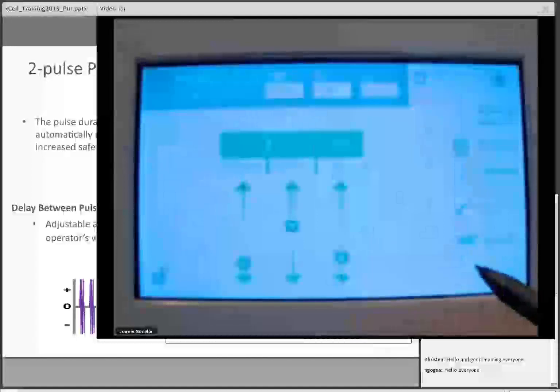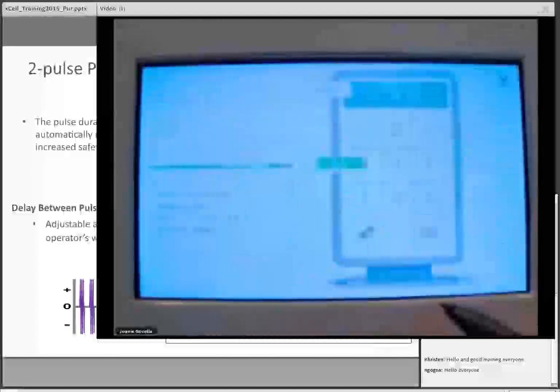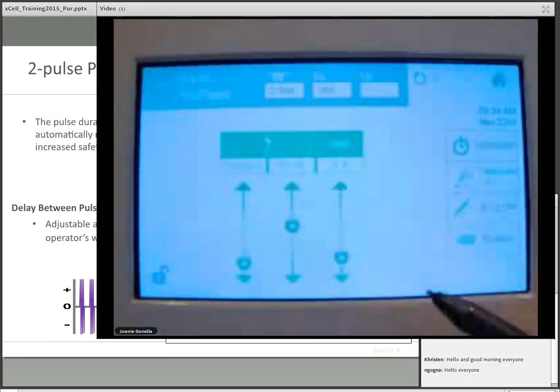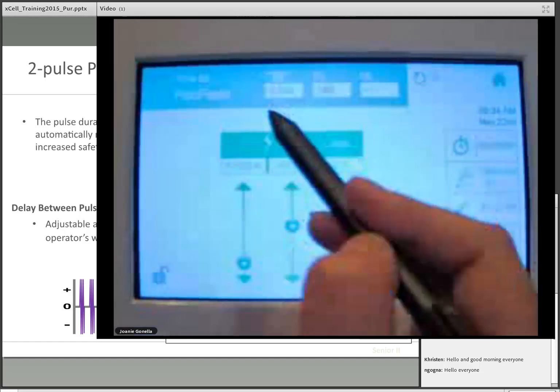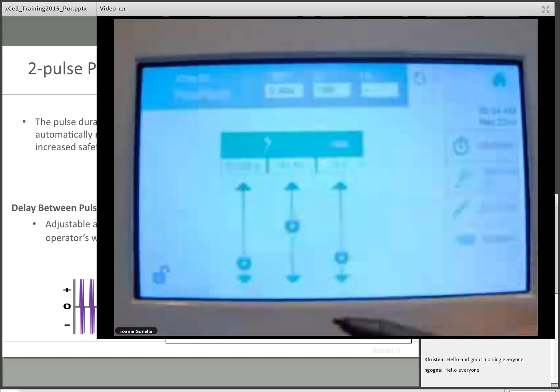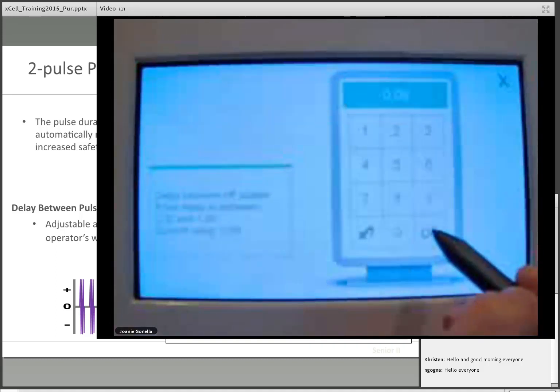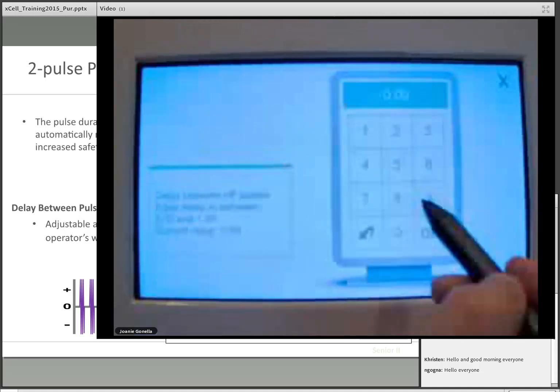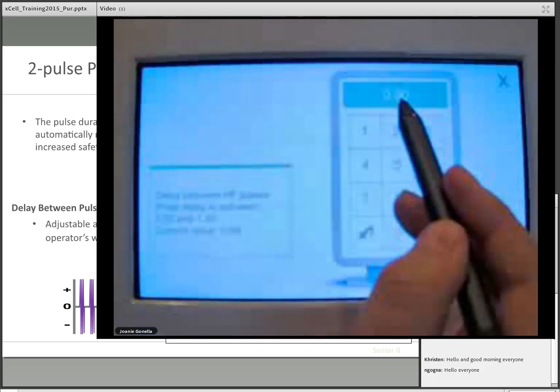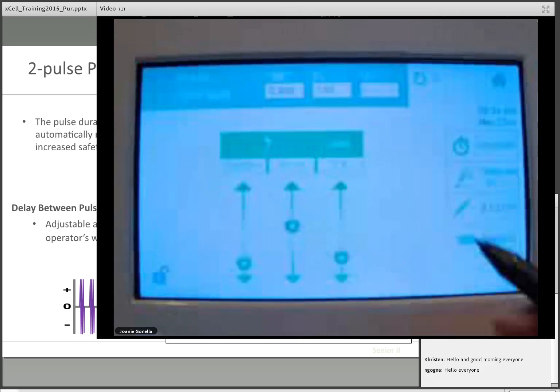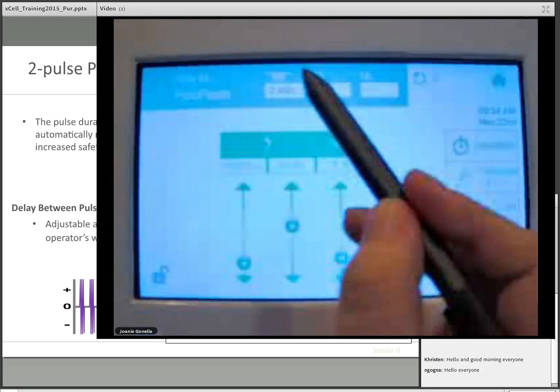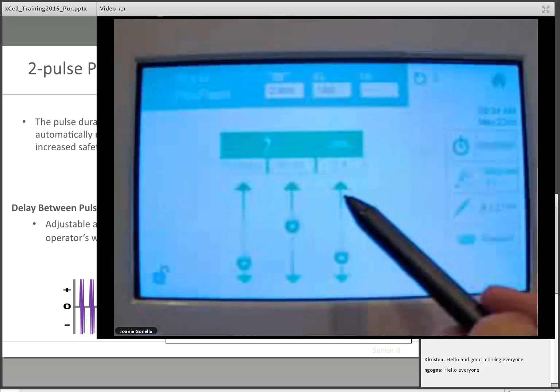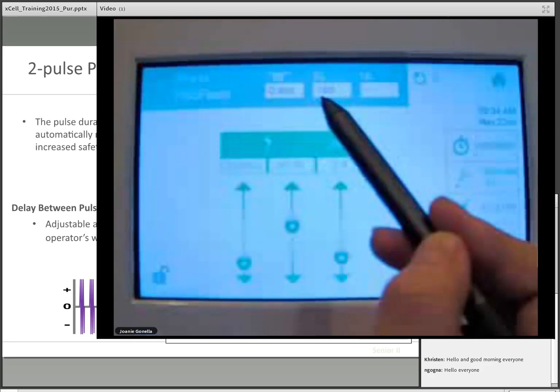And you can also tap directly on the number itself and then put in whatever you want, which was 2 pulses. So if I wanted 9, for example, I could do 9 and then put it here, and it will move it up for me. So that's a little too much, but let's say we just want 2 pulses. So with 2 pulses here, this showed up. This is my time in between my pulses. So it's on half a second, but let's say I want to do a little longer. So I can tap directly on that. And now this is where you want to be careful, because if you just do 9 and click OK, you'll notice that the 9 is in the hundredths position. That doesn't work. That would be pretty much 9 hundredths of a second. So we want 90 so that the 9 moves up next to the decimal. So double check when you're doing this that you're putting in the right time. Press OK, and now you can't really see it too well, but it says 0.90. So I've changed the time in between my pulses. I've changed the pulses here, and it recalculates the energy level for me automatically, and that gets displayed up here.